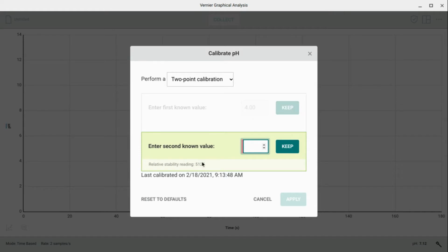Again, we have added the electrode to the second buffer of 7.00 plus or minus 0.02 on the pH level. So we will wait for this stability reading here to stabilize. Okay, so again, you can see here that this stability reading is pretty close to being stable, around 5171, 5172, somewhere in that neighborhood.